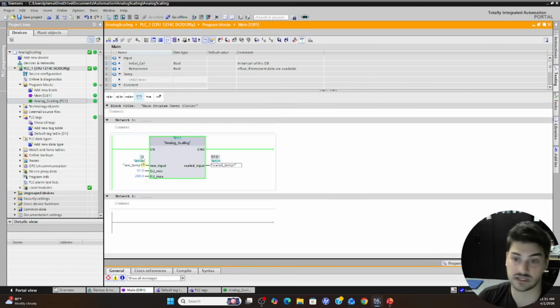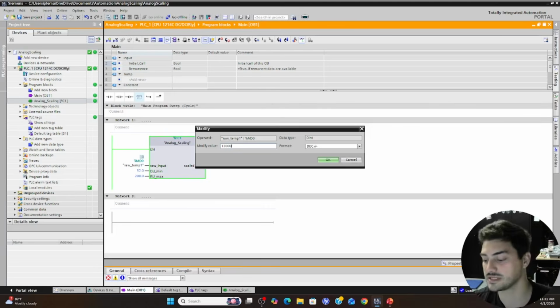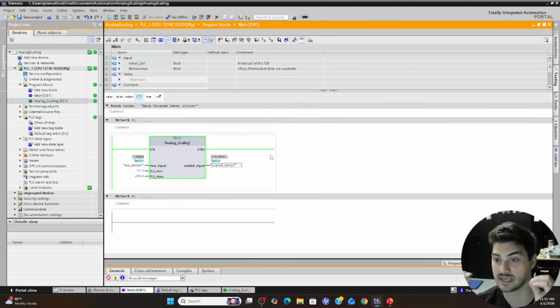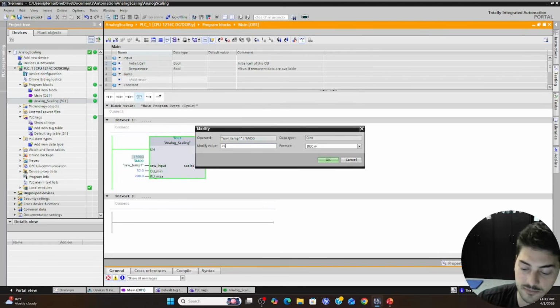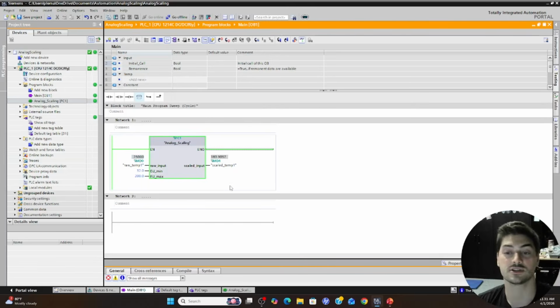Okay, so we're sitting there at 0.32, which is a good sign. Let's go ahead and throw 13,000 in here and look at what about middle span looks like, right? And it gives us, hey, okay, you're getting this electrical reading on your card of 13,000. That correlates to 110.99 degrees Fahrenheit. Nobody in the UK panic. And then let's get pretty close to max span, okay, 25,000. All right, it's 183 degrees.